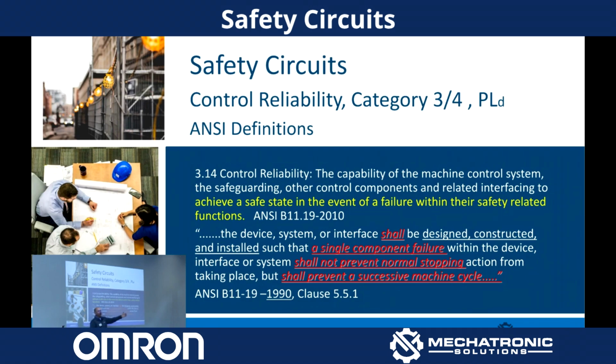Now, it can get as complicated as you want, and that will let your controls engineers dive into all the different ways they want to accomplish that. But with mechanical relays, there's a simple way to accomplish that, through redundancy and monitoring. Modern safety controllers have this built in. This methodology is designed into all modern safety controllers. It's not unique to the Omron brand. I wish it was, we'd sell a whole lot more controllers. But if you've got a safety controller from a competitor, that is accomplishing the same thing. This is how we're achieving it.